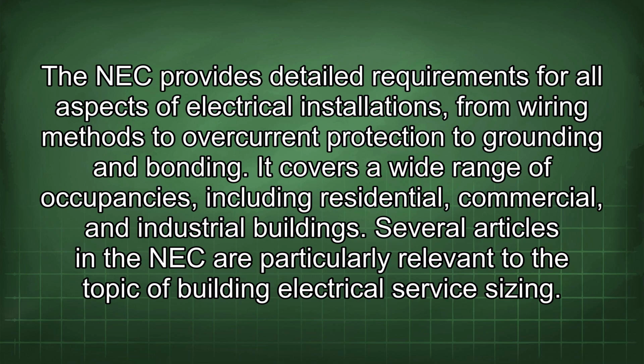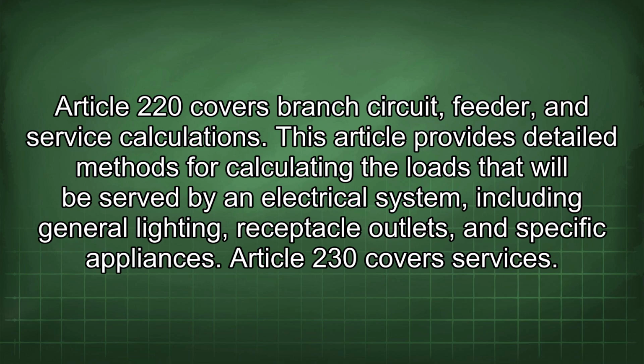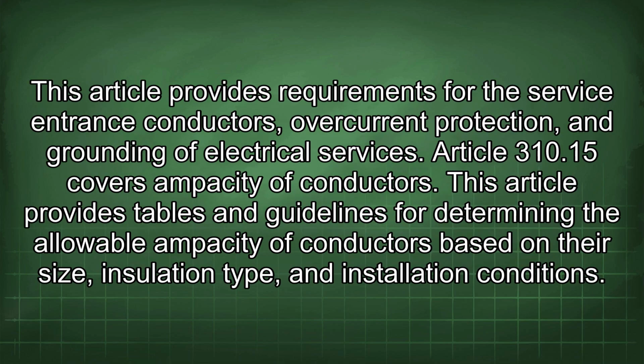Several articles in the NEC are particularly relevant to the topic of building electrical service sizing. Article 220 covers branch circuit, feeder, and service calculations. This article provides detailed methods for calculating the loads that will be served by an electrical system, including general lighting, receptacle outlets, and specific appliances. Article 230 covers services. This article provides requirements for the service entrance conductors, overcurrent protection, and grounding of electrical services.